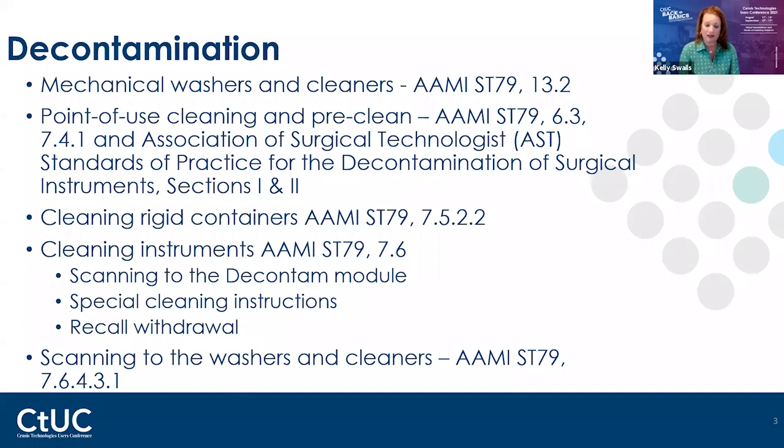So on to cleaning instruments. When you get your instruments into decontam, this is probably the one area I see that's missed the most. People are either not scanning the decontam at all, or they're scanning to a sink, but they're not scanning to the decontam module. Highly encourage everyone to scan to the decontam module, because if you have any clean instructions that are attached to a container, you're never, ever, ever going to see them unless you scan to that decontam module.